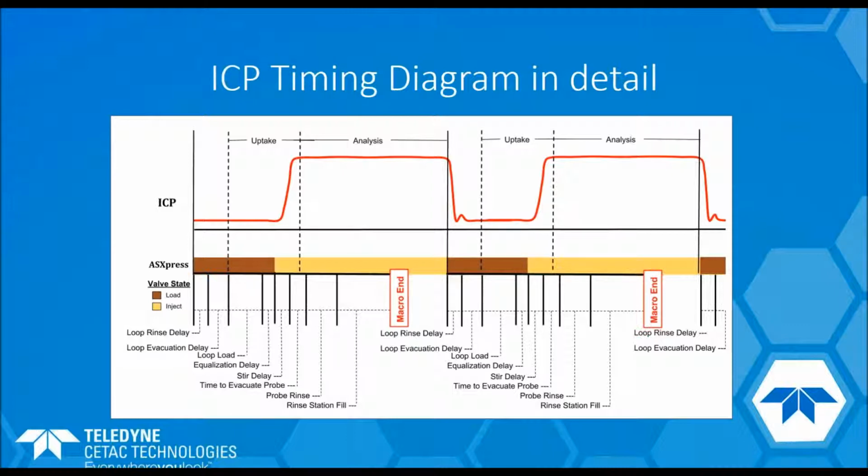So what you'll frequently see is you do get a very sharp drop-off in your signal intensity once your analysis is complete and the carrier starts pushing through. And you'll see that you'll even get this little blip, and that's fairly typical. It's the first 1 or 2 bubbles of rinse that come through will have a little bit of sample. You can see a bit of a blip, but it does incredible things for your washout time.